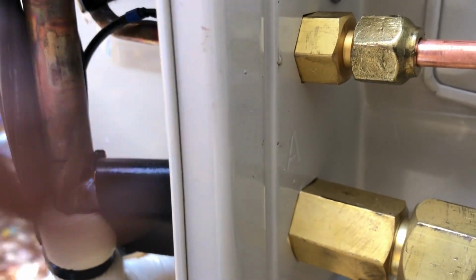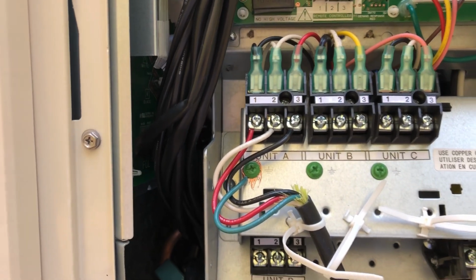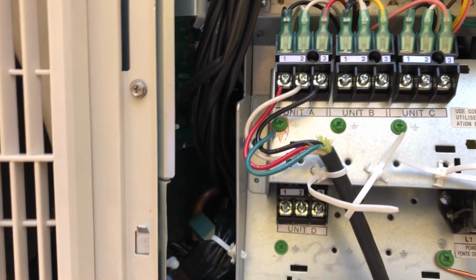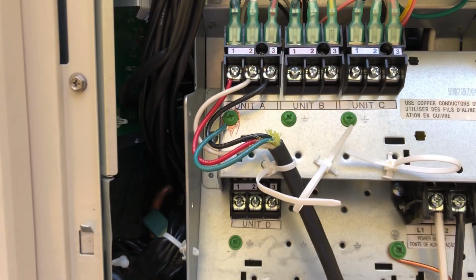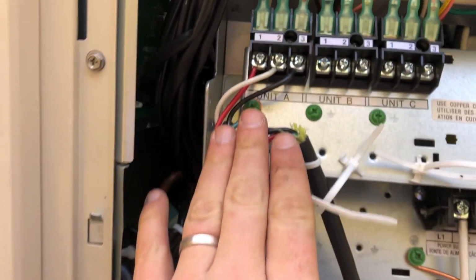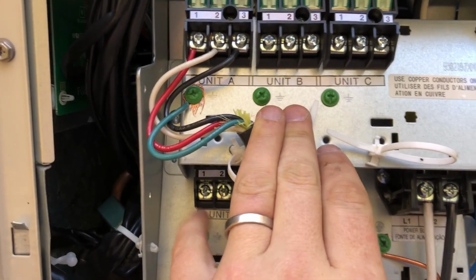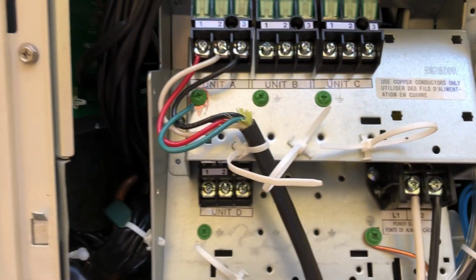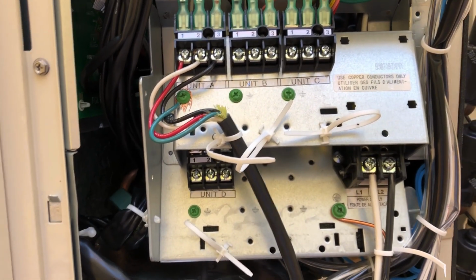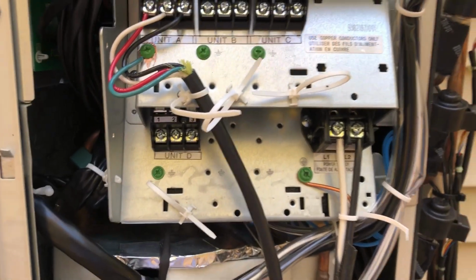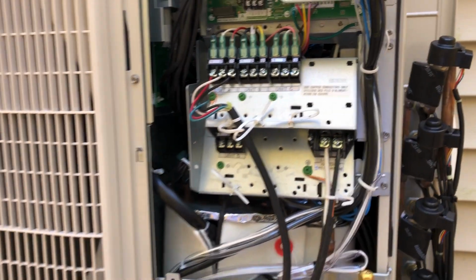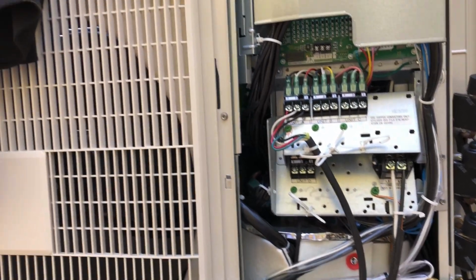They hook to the A. In this case, I always hook my first unit to the A. It's labeled right there - A for the first one, and then unit A over here. All that matters is that if you hook the line set to A, you hook the associated wire to that inside unit to the same one. The next one will be B, C, and D, since I've got 4 heads. That's really that simple - just make sure the same wire is hooked to the same line set that's running your HVAC to your inside unit. Otherwise, there's nothing more to this.